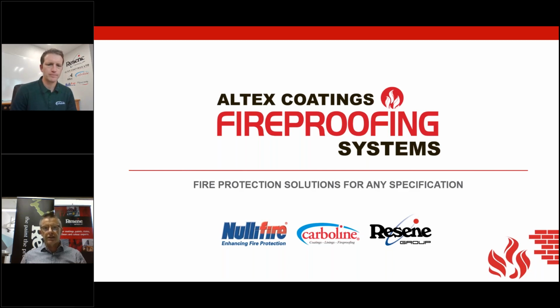I just want to add something there as well, as you talk about film builds. It's very critical for the contractors applying intumescents to be skilled, trained, and understand what they're doing. Unfortunately, all too often we have contractors who don't have a lot of experience in intumescent coatings, and it's very easy, should I say, to get it wrong very quickly with intumescent coatings around wet film thickness, equating to dry film thickness, and loading schedules, and then that's an initial application, and then site touch-ups by maybe not the contractor that applied the intumescent to begin with.